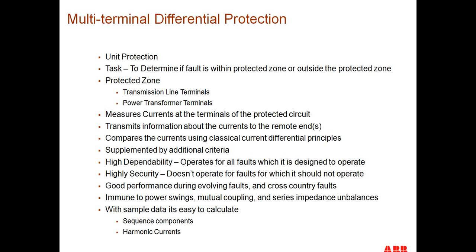Of course, the system has to have high dependability, which means it must operate for all faults within that protected zone. At the same time, it has to be secure, so it does not operate for any faults that are outside the protective zone. And also, by the nature of the beast, these should have good performance during evolving faults or cross-country faults involving separate phases on parallel lines. Because it's a current-only scheme, we're immune to power swings, mutual coupling, or that series impedance unbalances that we have to worry about normally.